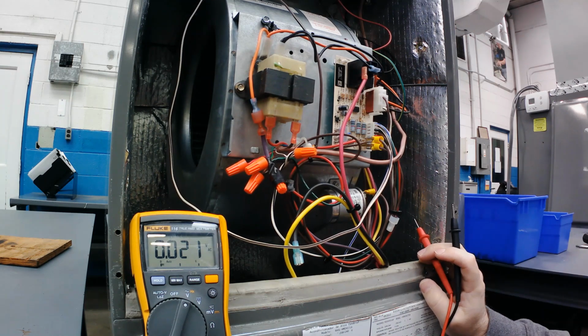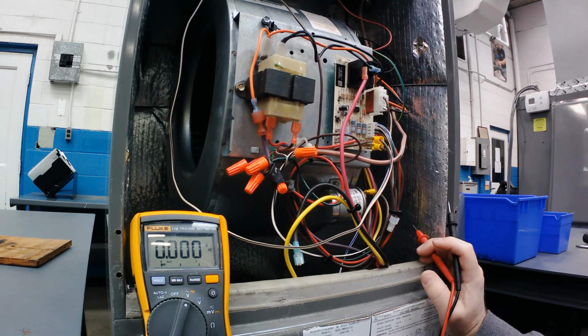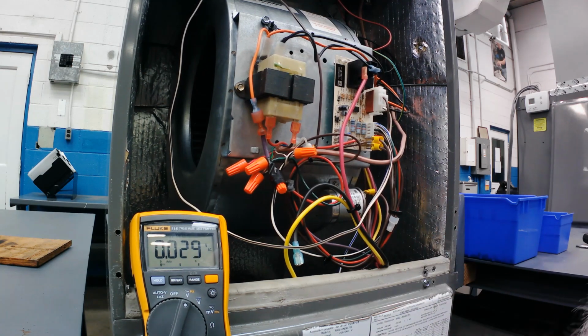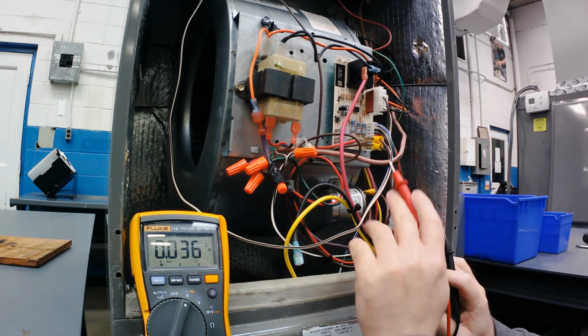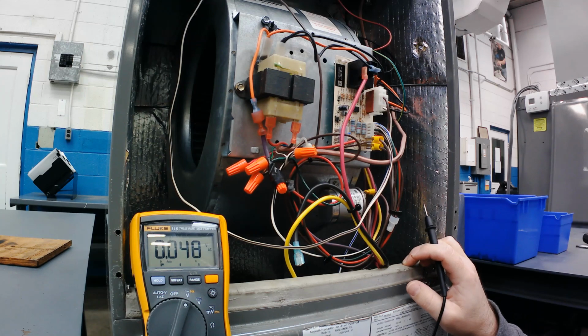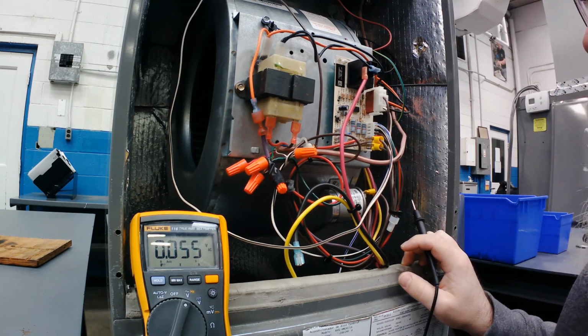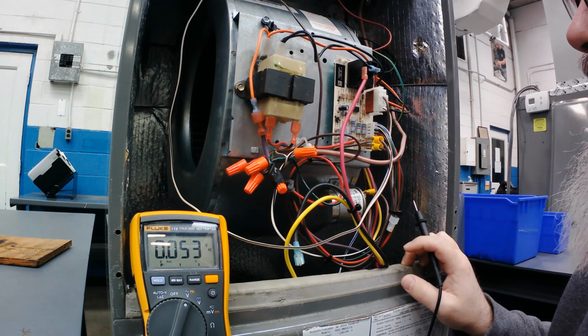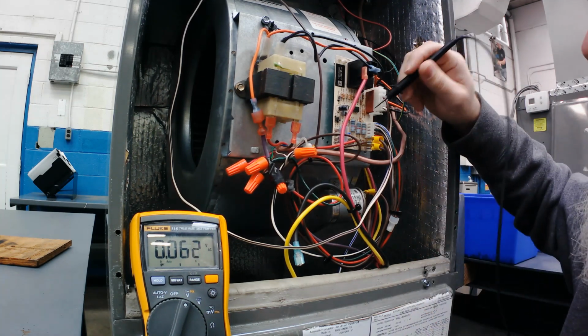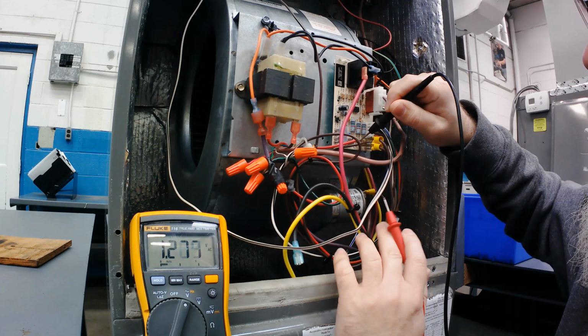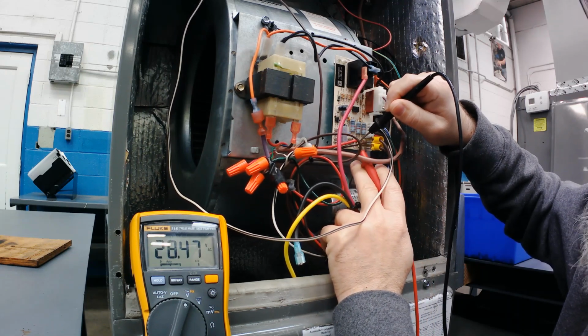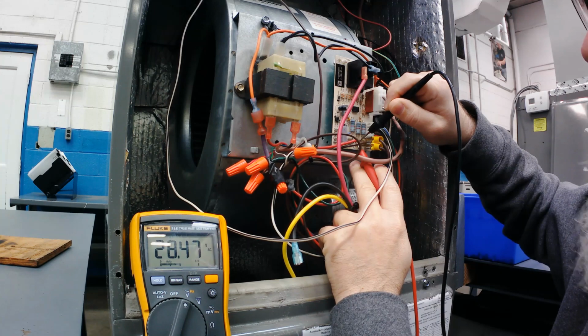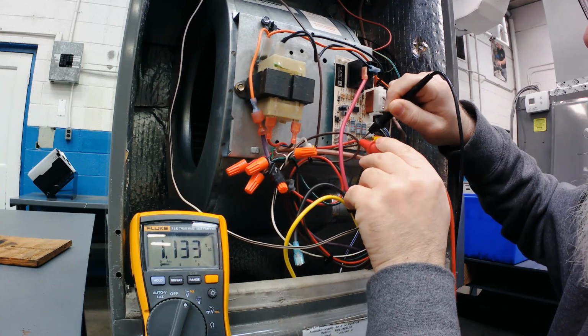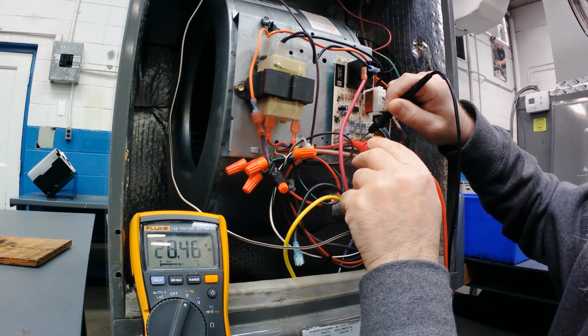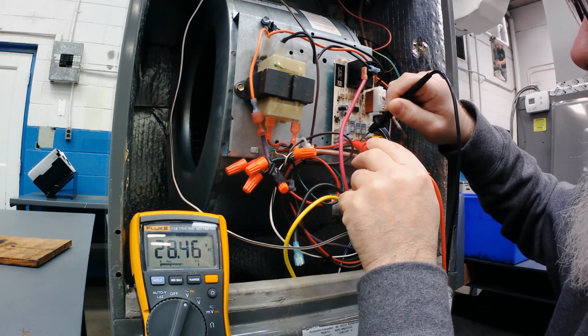Now the thermostat is off, so there's nothing going on, and I'm going to take this opportunity. We're going to refresh a couple little steps, right? One is the hopscotch. We always reference one side of power to the other one. So this fuse circuit, if you didn't just look at the fuse, or let's say that it was positioned so you couldn't see it being blown or whatever, I will leave one lead on common, and this transformer R brings power from the transformer into the board on that terminal, and then the circuits on the board go to the fuse. So I can check power going into the fuse. Okay, so I still got 28 volts.